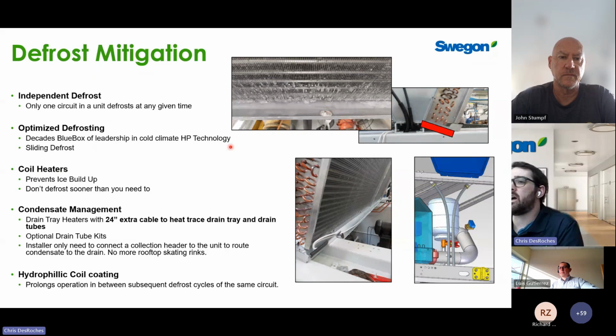In terms of managing that condensate after, we have coil heaters at the base of the coil, you can see up here. So if we have any water that hasn't made it to the drain tray, our drain trays are sloped, but we actually add electric heaters at the base of the coil. Small wattage, but just basically to ensure that we don't have ice building up here, because once you start building up ice on a heat pump, it's going to accumulate and get worse and worse. So we want to prevent that from building up in the first place.